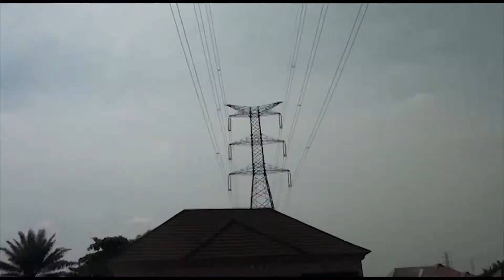TCN has basically two high tension lines, which is 330 kV and 132. For the 330, the setback is 25 meters this way and 25 meters this way from the center line. For the 132, it's 15 meters this way and 15 meters this way from the central line. So altogether that makes it 50 meters for 330 and 30 meters for 132.